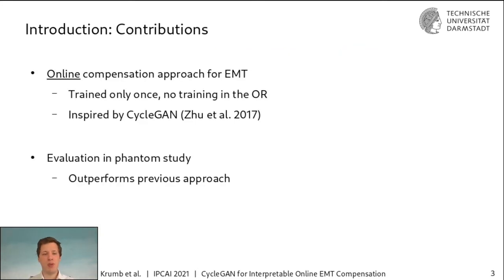Our contributions are an online compensation approach for electromagnetic tracking. Online, in this case, means that this approach only needs to be trained, or calibrated if you will, once. There is no training necessary to be performed in the operating room before the actual intervention, so we can consider this an out-of-the-box approach.